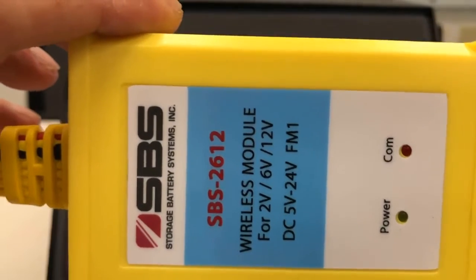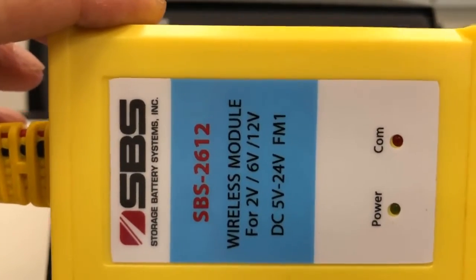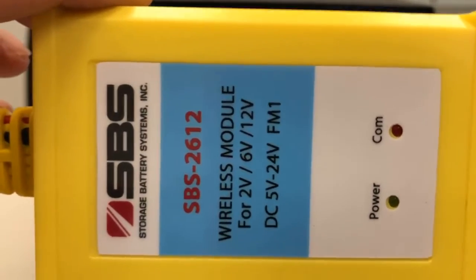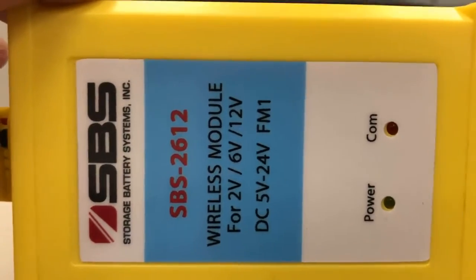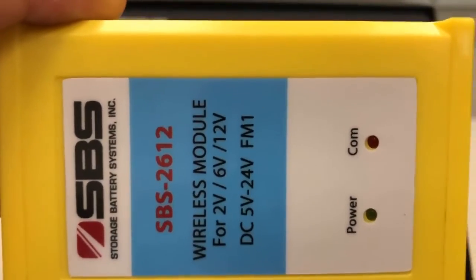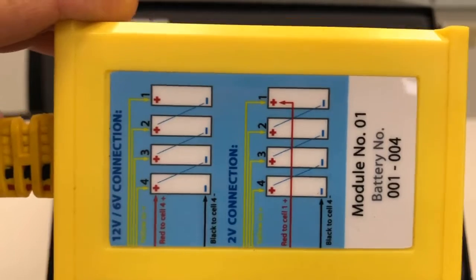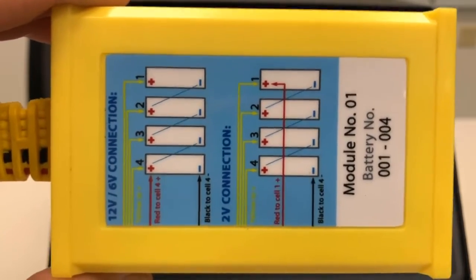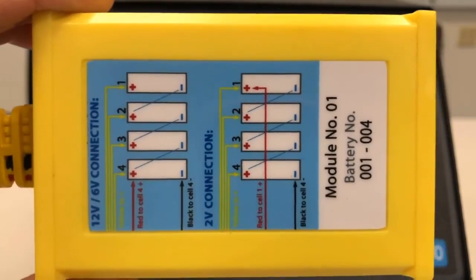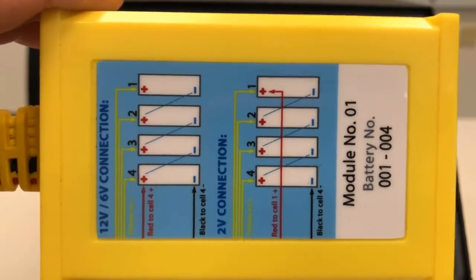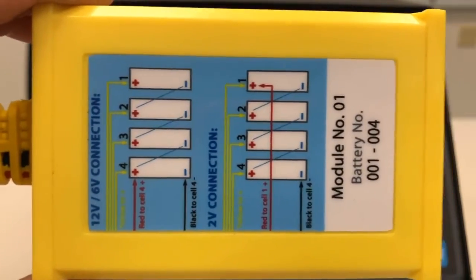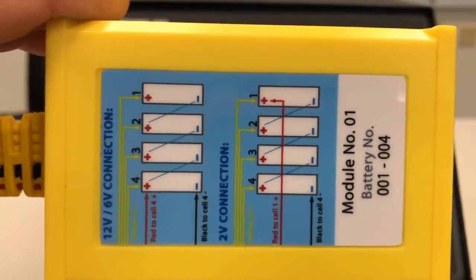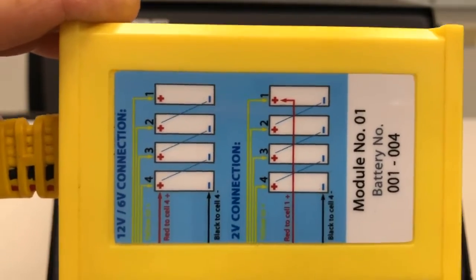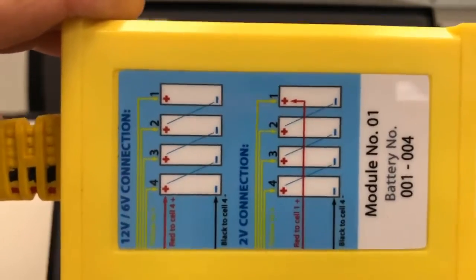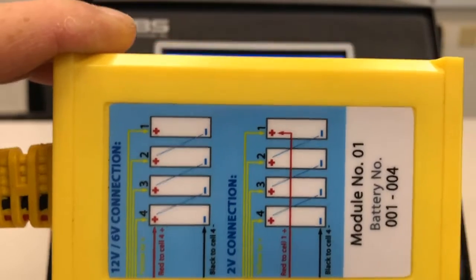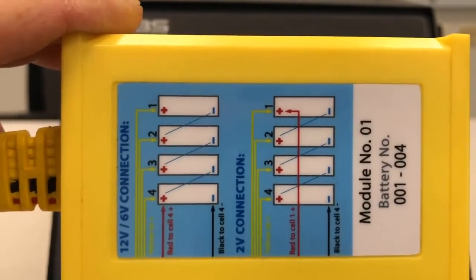The fronts of the wireless modules will have an FM number. That tells you the frequency that the module is communicating on to the load bank. The back side of each wireless module will tell you the battery numbers or cell numbers that will be monitored by that module. In this example, batteries 1 through 4, or cell numbers 1 through 4, will be displayed on the unit once the module is connected to the batteries.